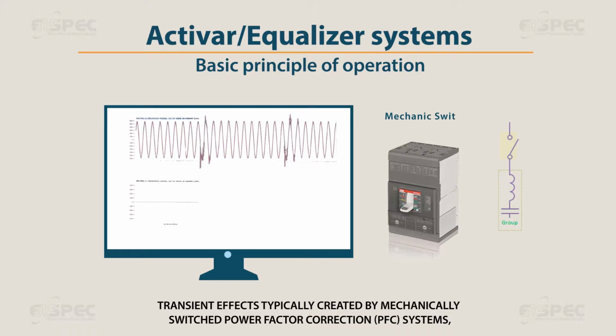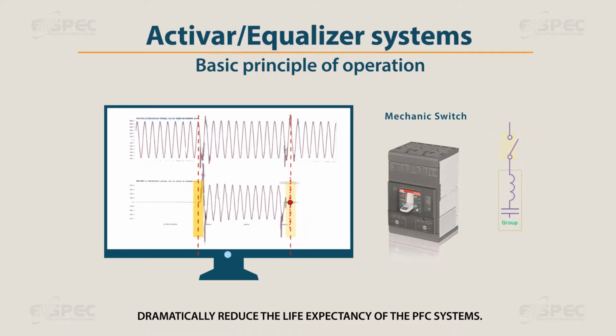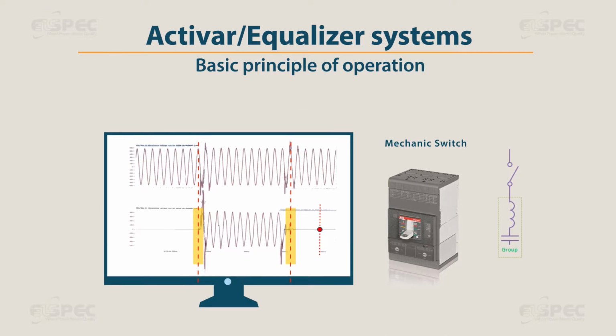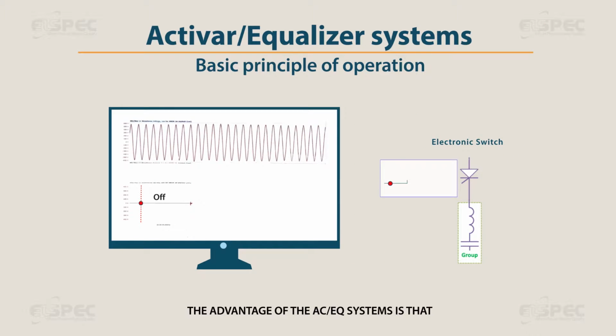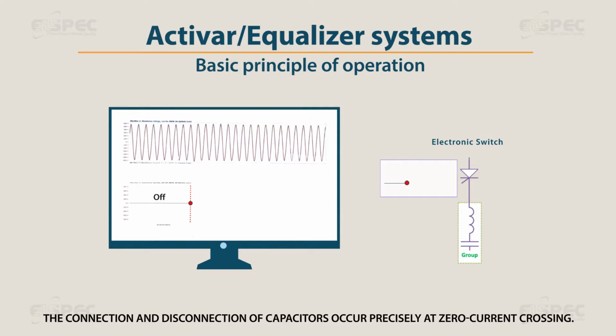Transient effects typically created by electromechanically switched power factor correction, PFC, systems dramatically reduce the life expectancy of the PFC systems. The advantage of the AC EQ systems is that the connection and disconnection of capacitors occur precisely at zero current crossing.